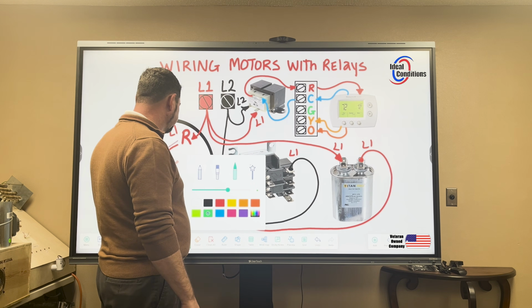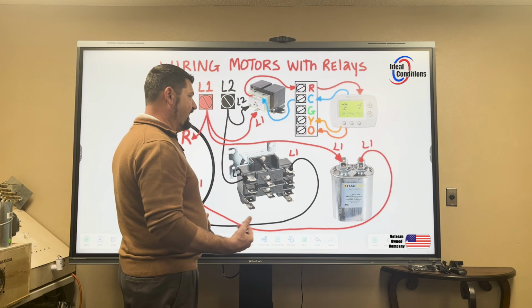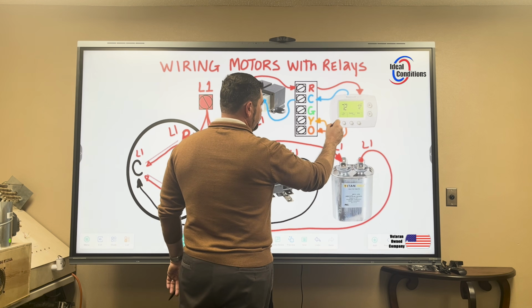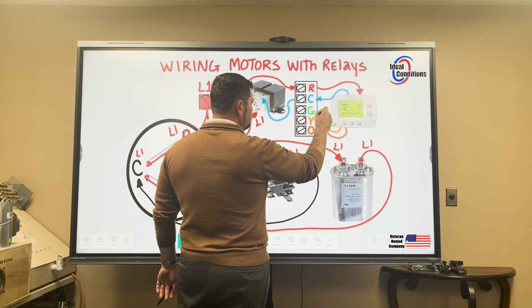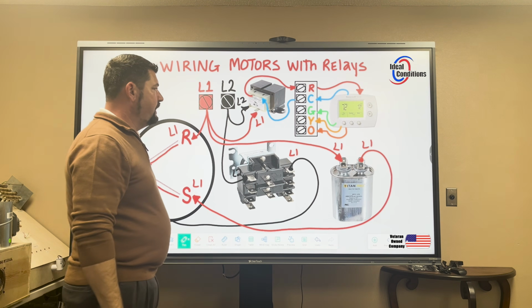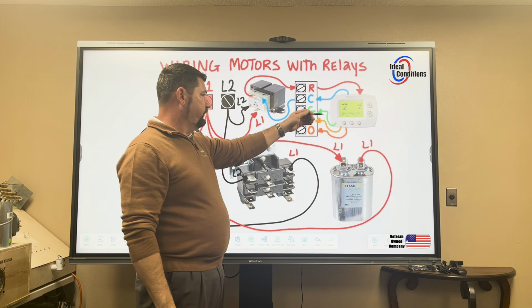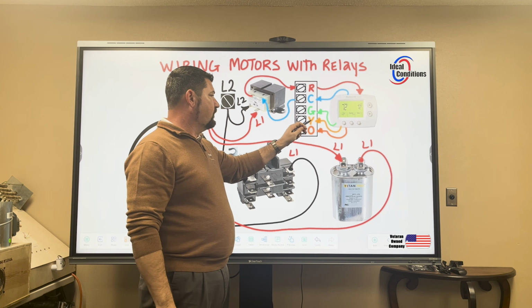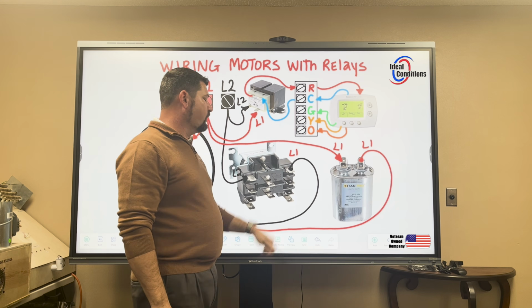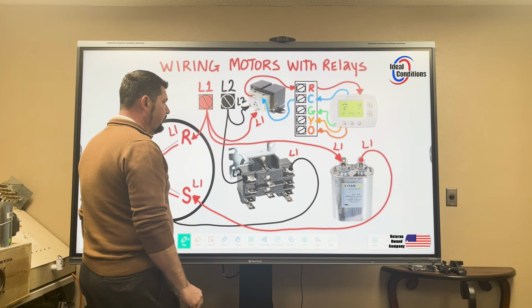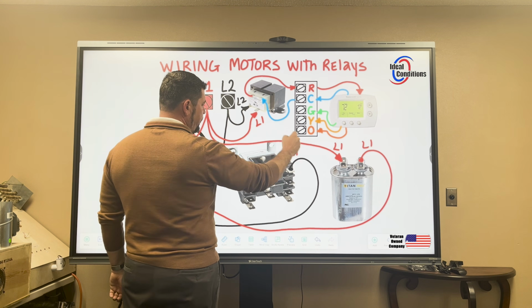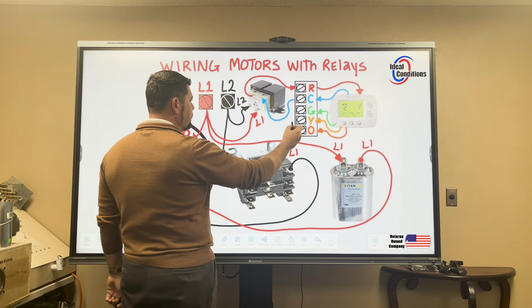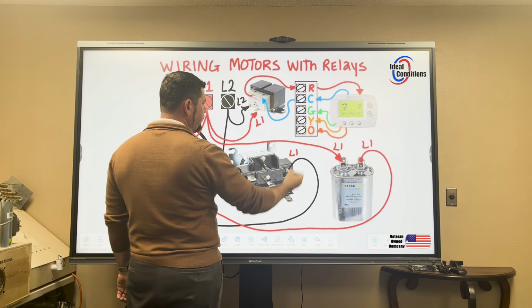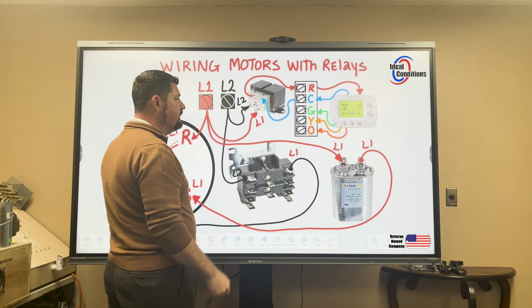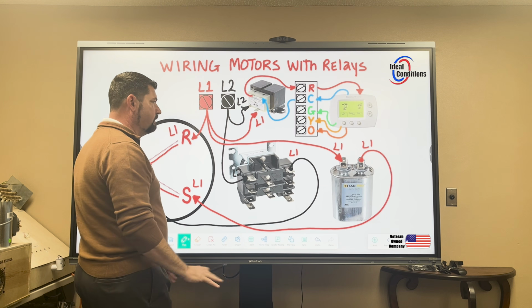The only one that we're concerned about in a very standard application like this would be just the G call that the thermostat provides. And as long as it's programmed correctly, you'll always get a G call in the event that it needs to run in heat or cooling, right? And so once we get this G call, this is what we want to wire our relay to. Yes, the fan needs to run anytime you have the rest of these, but primarily the G call. Because what if you just want the fan to come on by itself?